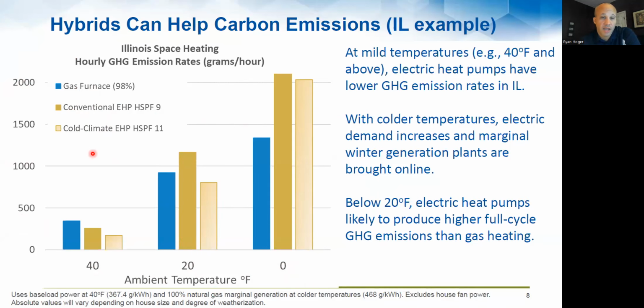We have 3 options of systems on here. This light colored one is a cold climate heat pump. And in this case, it has an HSPF, an efficiency, of 11. We have a traditional heat pump. And by the way, this cold climate one was inverter driven. Doesn't have to be, but it almost always will be. This conventional one was 9 HSPF, which is actually a pretty good standard heat pump. That would get a utility rebate where I live, and I think it would where you as well. So it's a pretty good non-cold climate heat pump, meaning it's not optimized for cold weather, probably not inverter driven.